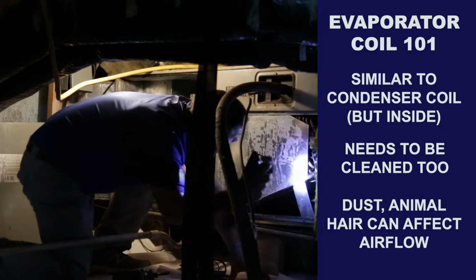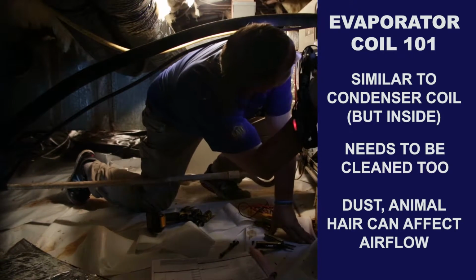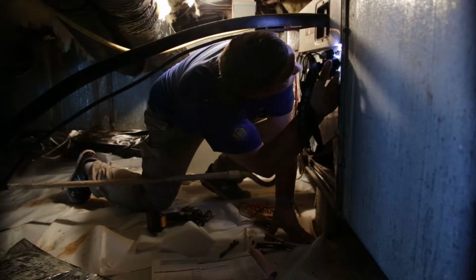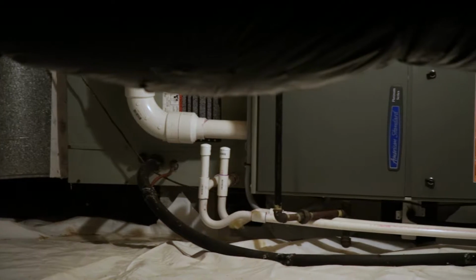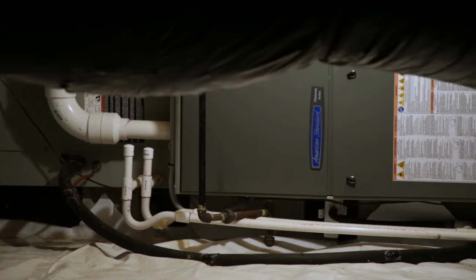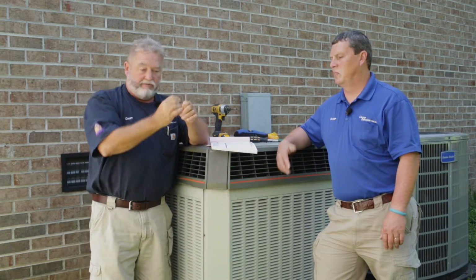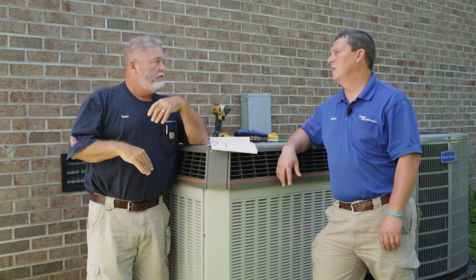Make sure it's clean. Fins should never be crooked or dirty or bent unless somebody's been in there and messed them up. Next thing on the evaporator is make sure that drain line's flushed out. Water's got to go somewhere off the coil. A lot of times traps need clean outs now, don't they? Yeah. So we go in there, we cut out, put a little clean out trap, and you take some compressed air or water and blow air through that trap, brush it, anything to run down it to clean it.